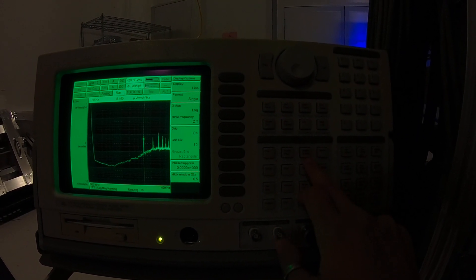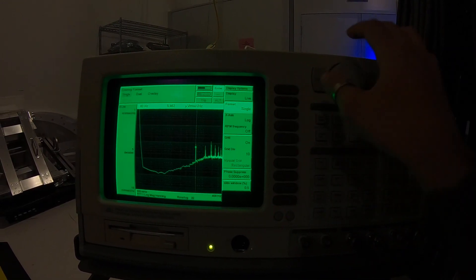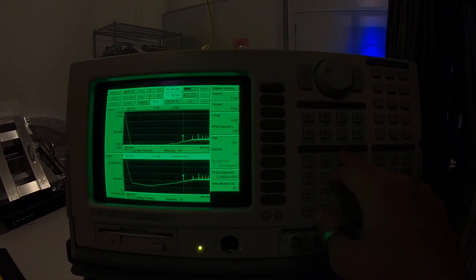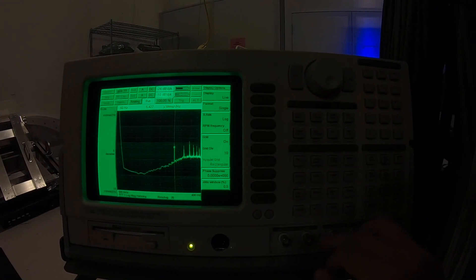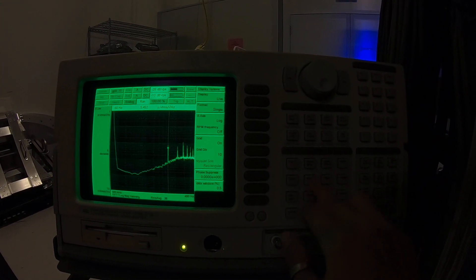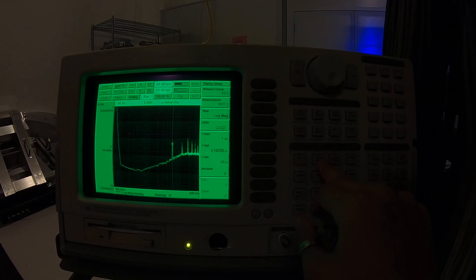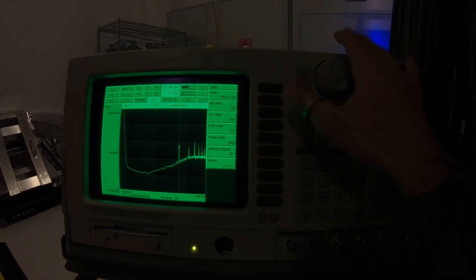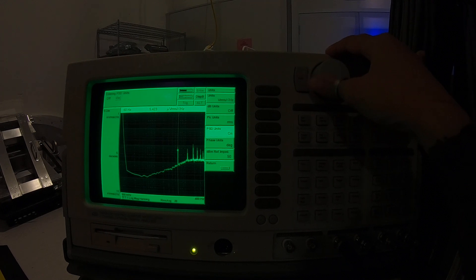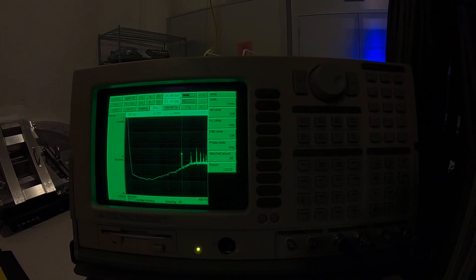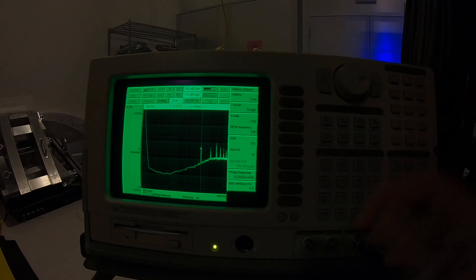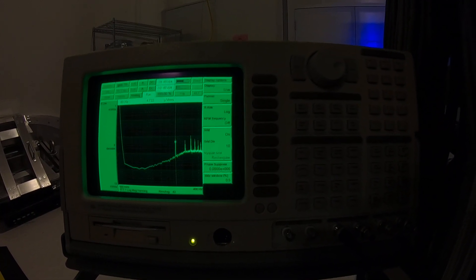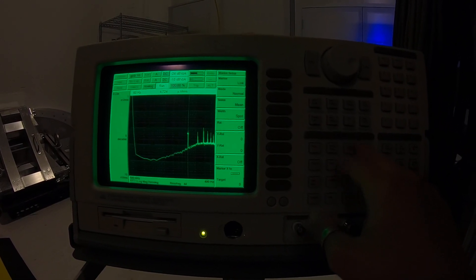First you need to display, just go to display option, format is now dual. Actually, there's a trick here. In display setup measurement group, you want to make sure that your PSD unit is off. Otherwise, the transfer function unit is not going to make any sense. I think it's some kind of bug that hasn't been fixed in like the past 20 years or so.